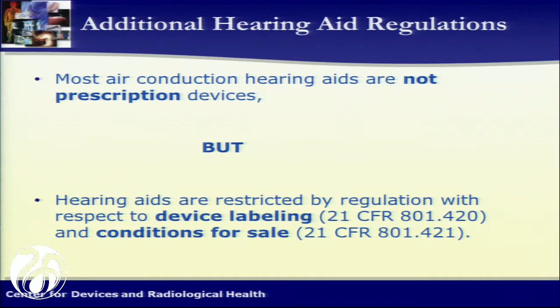So here is the regulation regarding labeling, 21 CFR 801.420. There is a requirement within this labeling regulation for the manufacturer to develop a user instructional brochure, and the regulation outlines the content of that brochure. In particular, there have to be very well-defined instructions for use. This includes a diagram with all of the different components and functionalities of the hearing aid described, how to insert and remove the battery, how to maintain the hearing aid, and conditions to avoid damaging the hearing aid, as well as the expectation that an air conduction hearing aid will not restore normal hearing.